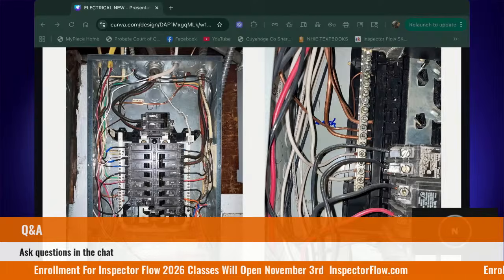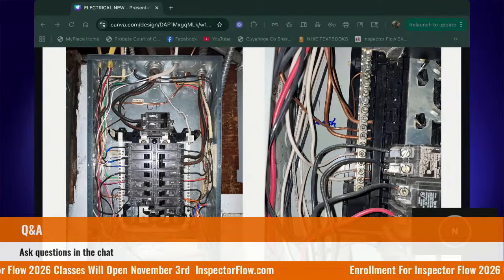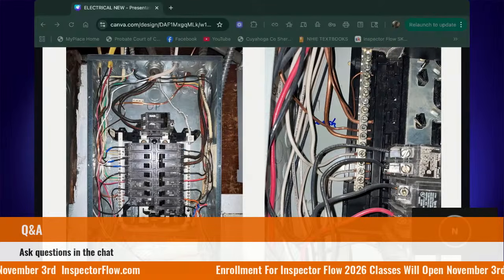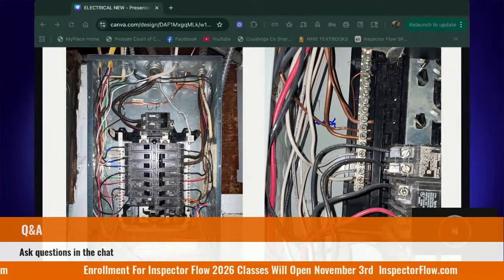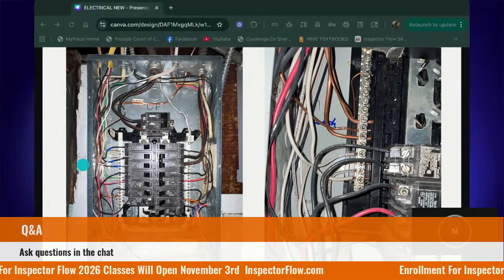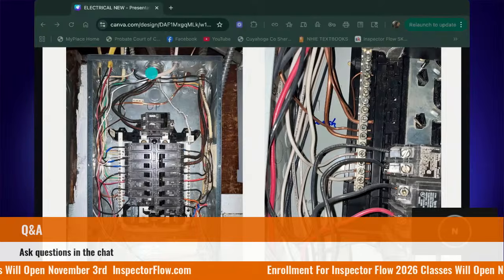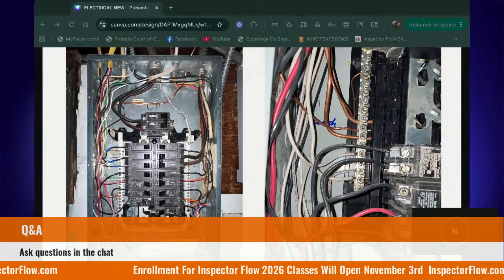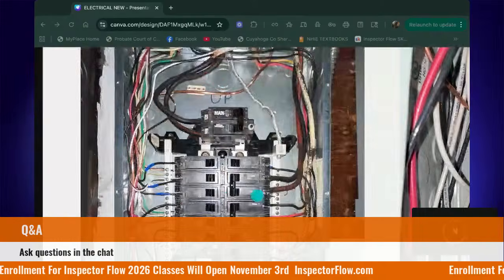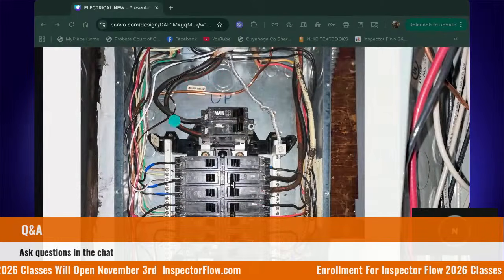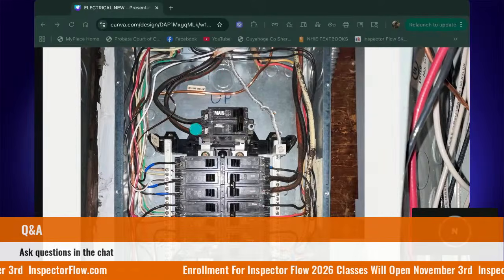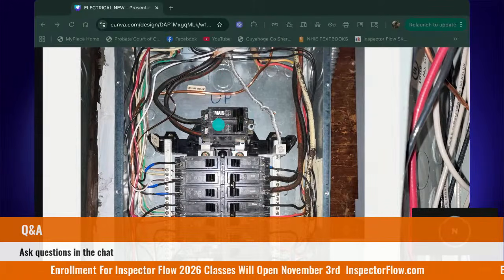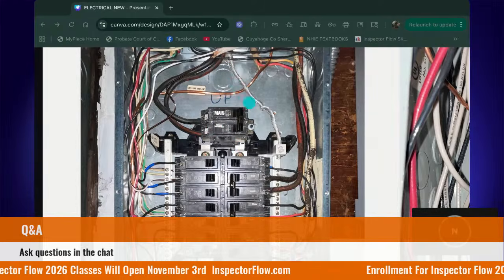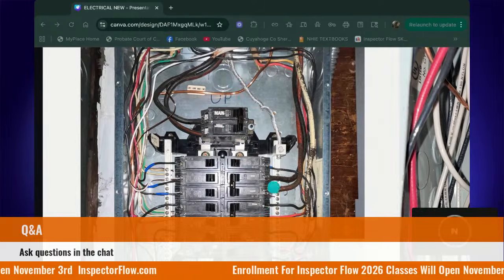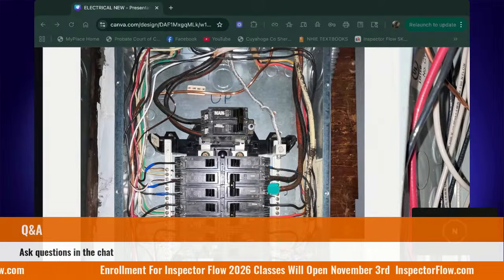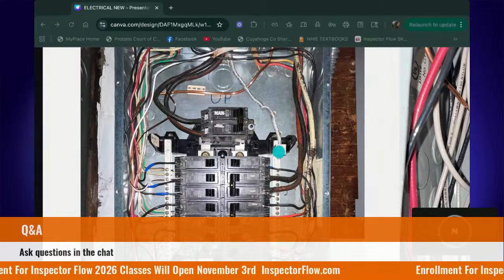So I will acknowledge, at the beginning it probably will be a little intimidating to remove the cover, but it's important, because look, this is what you see when the cover is off. These are our two hots coming in, connected, our main lugs. This is the main disconnect. See here, main. And then this is our neutral connected over here to the neutral bus bar. Okay, that's where we start.